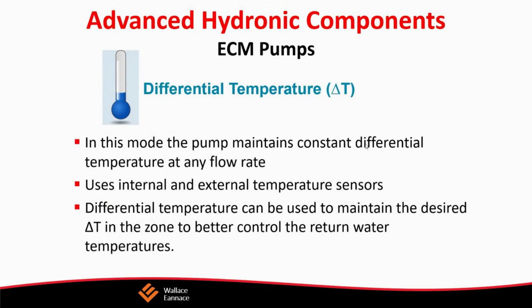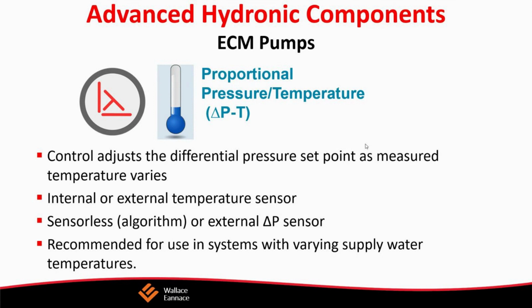Desired pressure can easily be set by the user interface. It's the default operating mode. It's sensorless. This is all sensorless. It uses an algorithm to calculate exactly what its pressure is. It does have a sensor in there. It's recommended for use in systems that have smaller constant pressure losses. A good example is radiant heating and cooling.